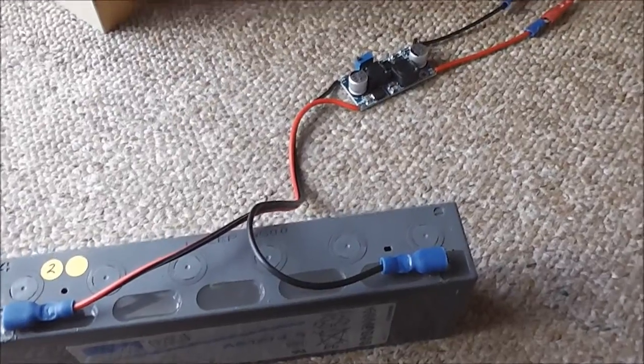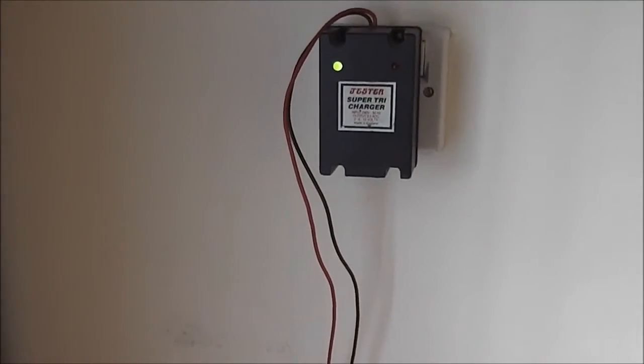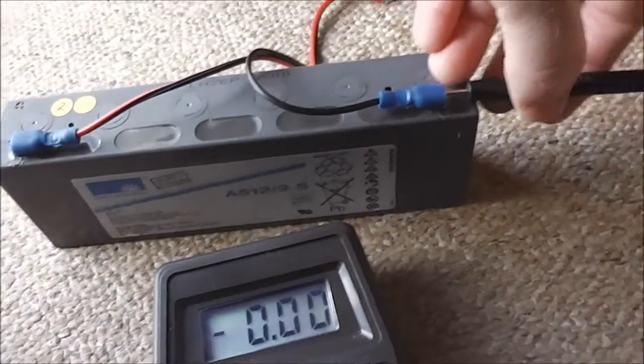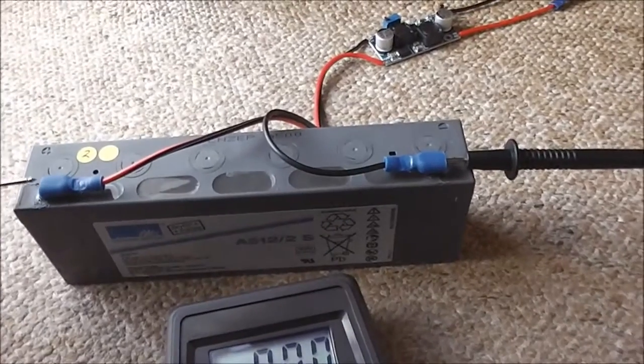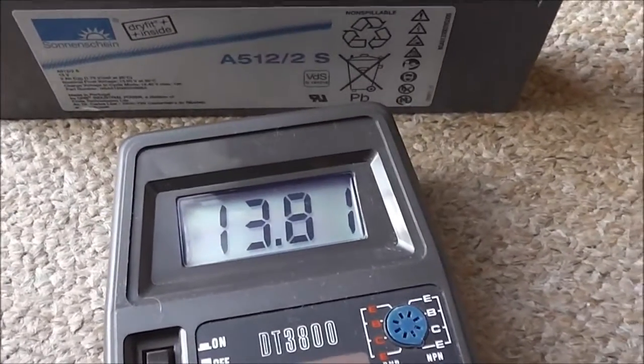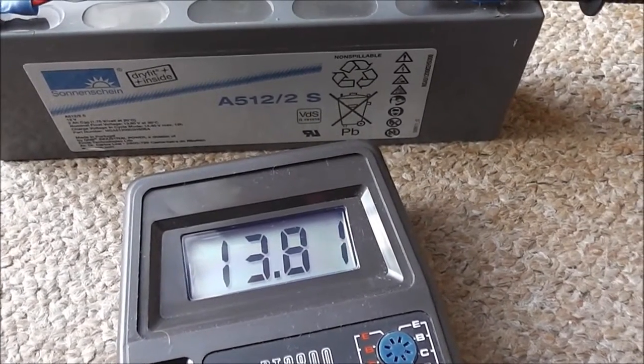Okay, so I've wired that in. There she is. Wired it up to my charger and I'll put the battery test leads in. There you go. A proper 13.8V float charge.